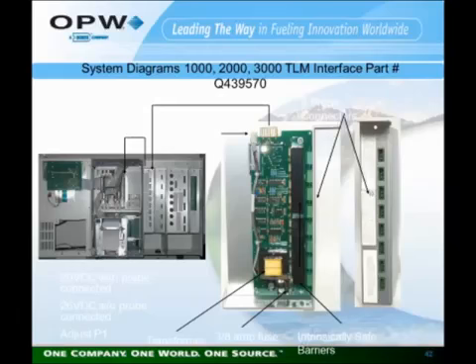The power supply on the TLM interface module is a constant output power supply, so every connection for probe on this module should show the same voltage whether there's 1 probe, 2 probes, or 8 probes connected. Should the voltage drop as more probes are connected, there's a problem with the power supply and this whole module will need to be replaced. If the voltage is low but constant, then it can be adjusted using an adjustment that's next to the transformer on the board.